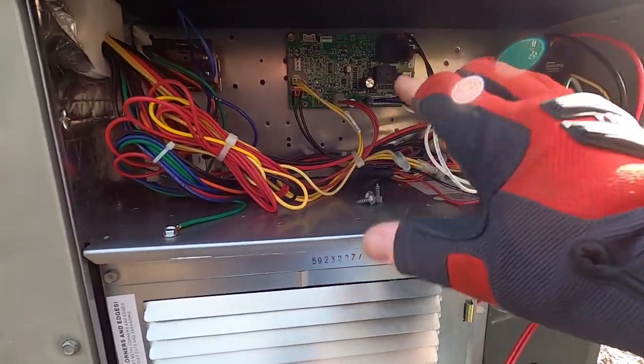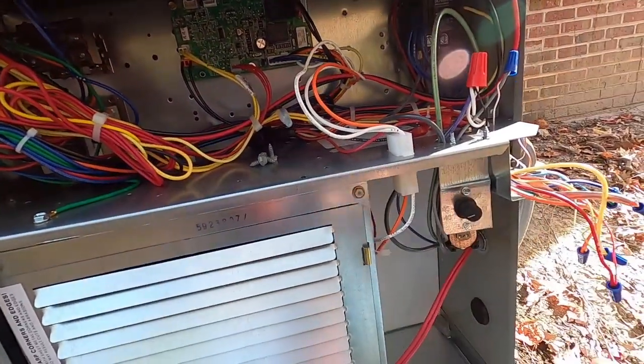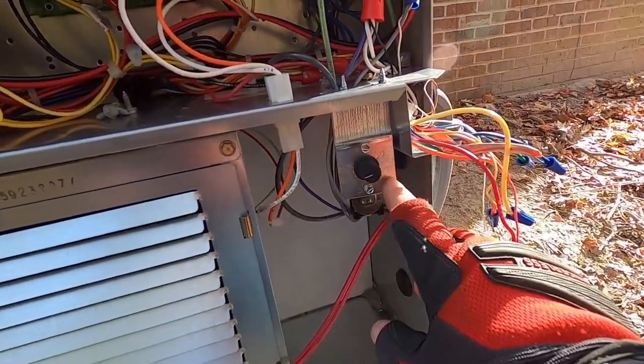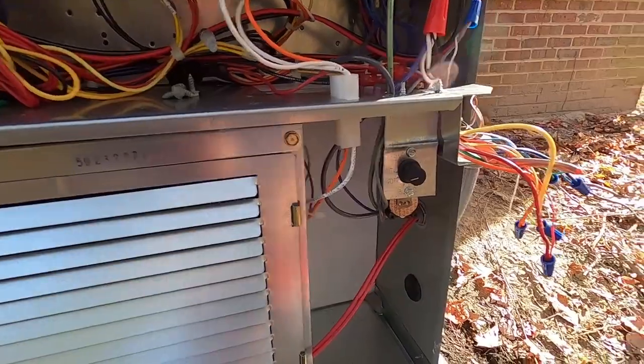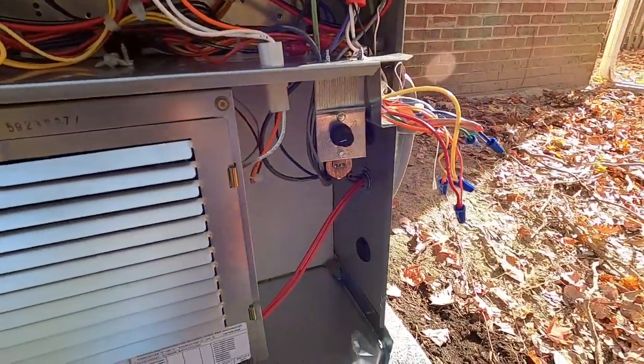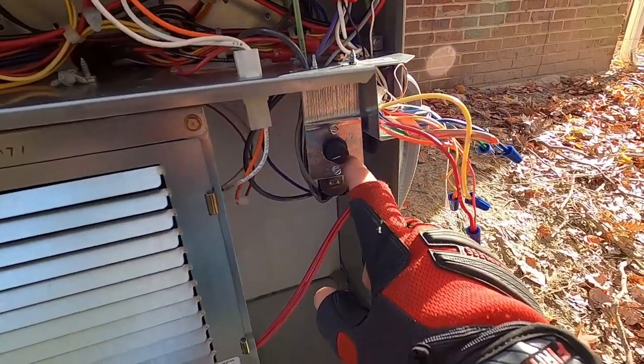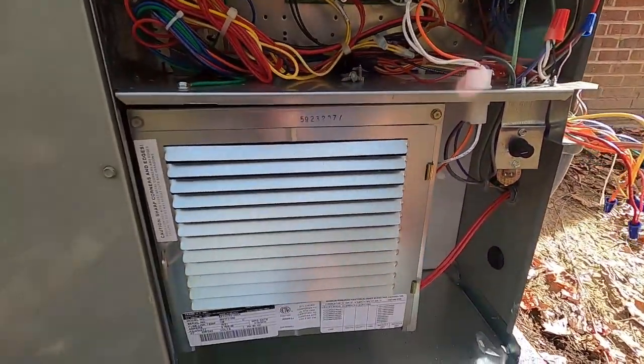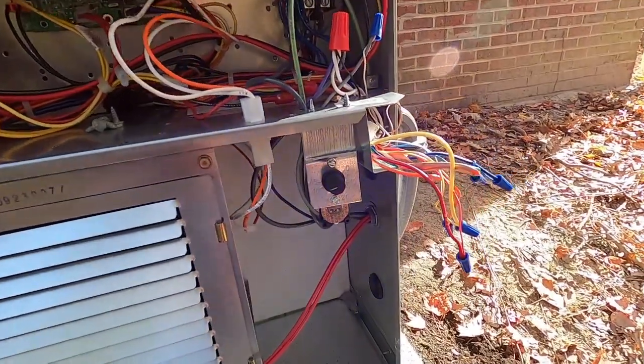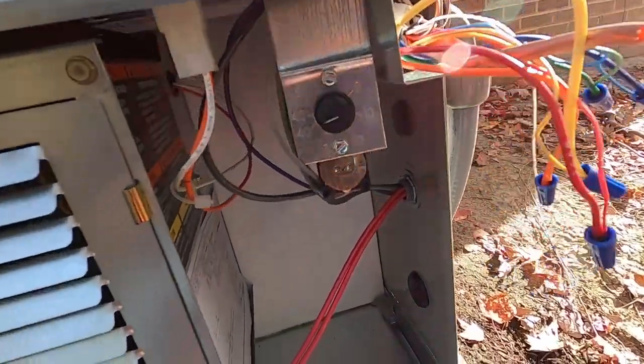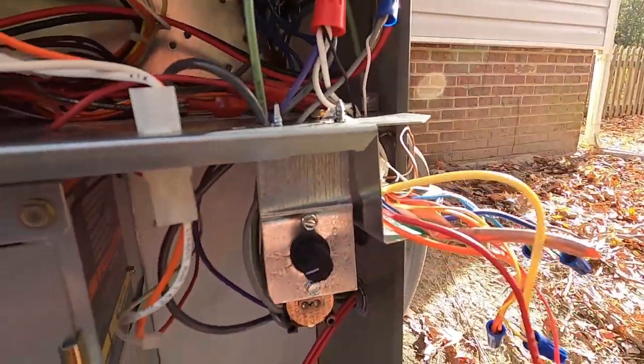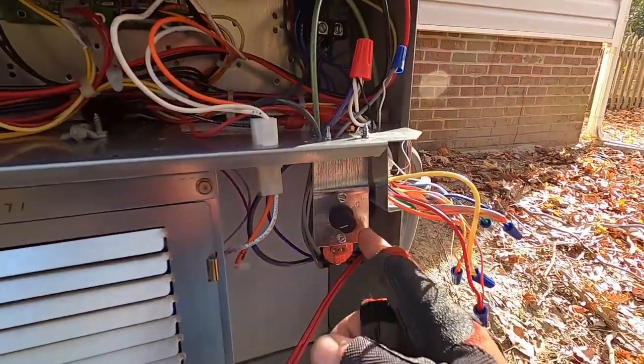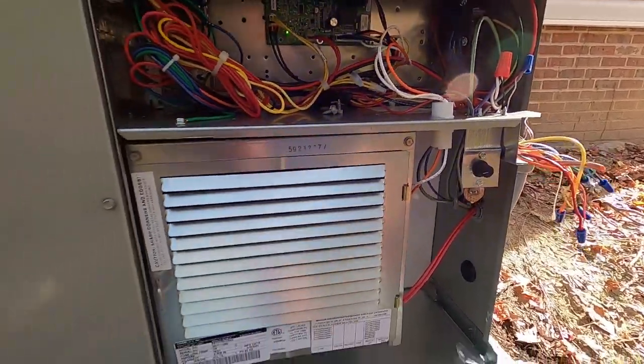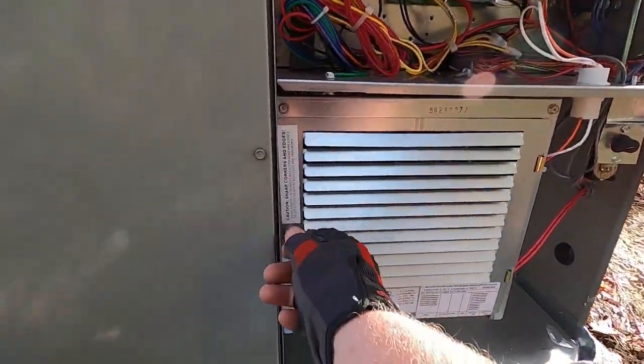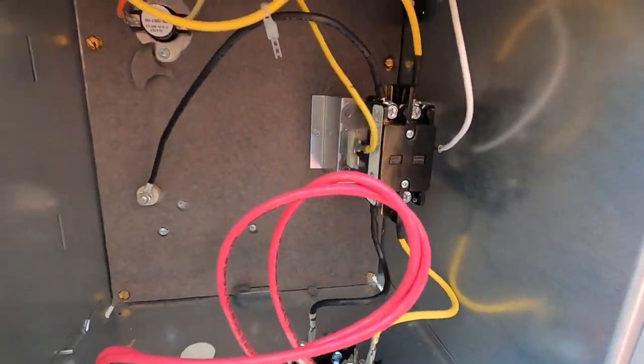And on colder nights, the heat's running, the inside of this gets warm air blowing through there, the electronics, things like that. It's really hard. I've yet to see one of these drop low enough on a cold night to allow the heat strips to actually come on. So I'm gonna have to come back, put the correct outdoor mechanical switch on this. So that's explaining that for people that were watching it a while ago or a few minutes ago when I was talking about that. If I went too fast for you, it's just a mechanical way to lock out your auxiliary heating or your electric heat strips on these units so that they don't come on until it's cold enough for them to be on.